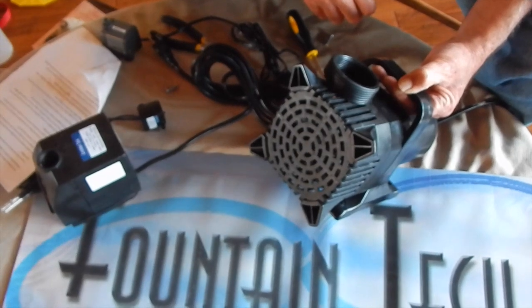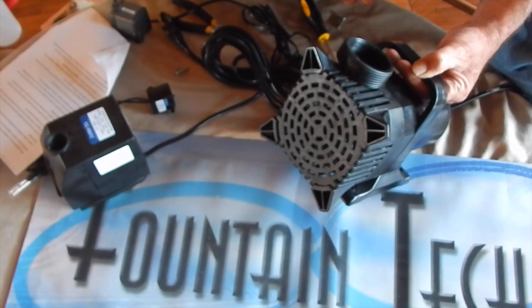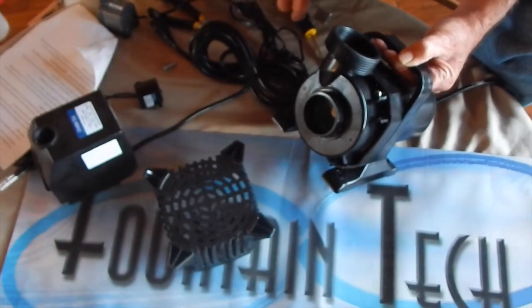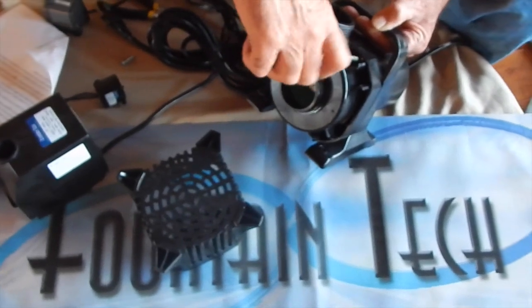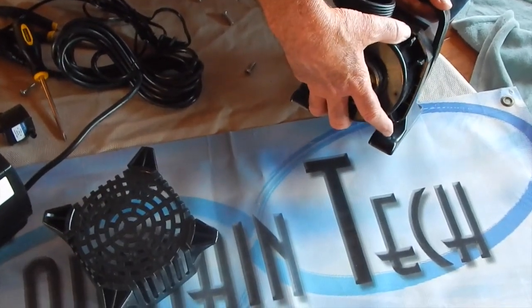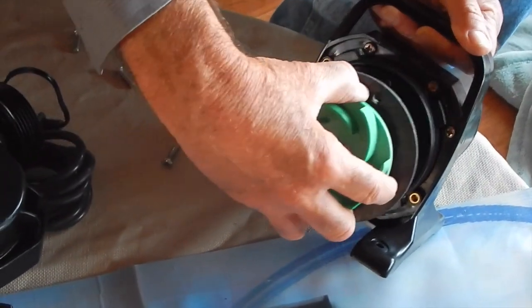For our larger pumps, you'll find you must take out four screws. This is for our Aftec 1900, 3500, 6000, and 8000 pumps. Pop off the cover, taking out the screws — one here, one there, one there, one there. Once you've removed all four screws, you turn the inner cover counter-clockwise and pull it off. Now you'll see the impeller.